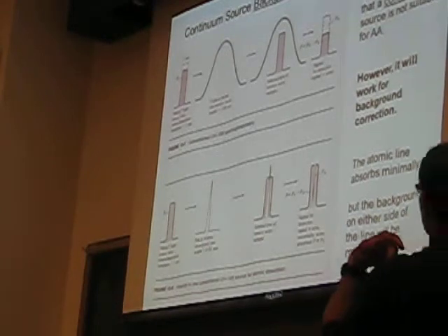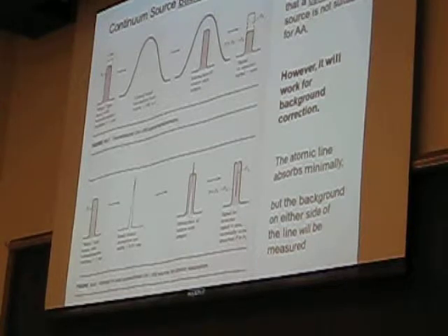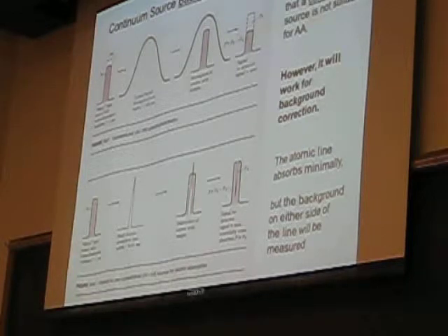But in the case of atomic absorption, we know, and I pointed out, that we don't use a deuterium arc lamp or a broadband emission source to generate light because the light is too broad and spread across a wide range of wavelengths, right? And so we don't use deuterium arc lamps to generate a source of radiation that's going to be absorbed, but we can use the deuterium arc lamps to generate a broadband radiation that can allow us to measure background absorbance and as a way to try to correct for the non-atomic absorbance.